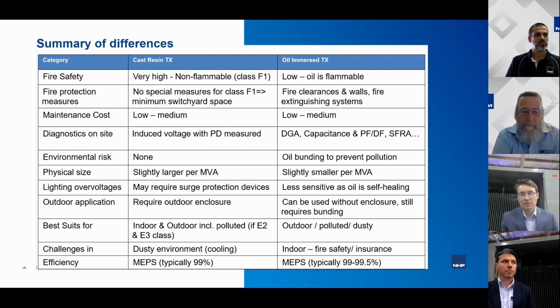With over voltages, like I already mentioned, there are more risks for cast resin transformers, because an over voltage event that exceeds the BIL level of the insulation will result in a catastrophic fault of this insulation. Using surge arresters is very important, while oil transformers are actually self-healing in the event of over voltage. Outdoor applications, we already mentioned oil transformers have an advantage, though cast resin can be well used with an outdoor enclosure in suitable environments. And that links also to environmental categories such as E2 and E3, which allow cast resin transformers to be used in more humid environments or close to seawater.